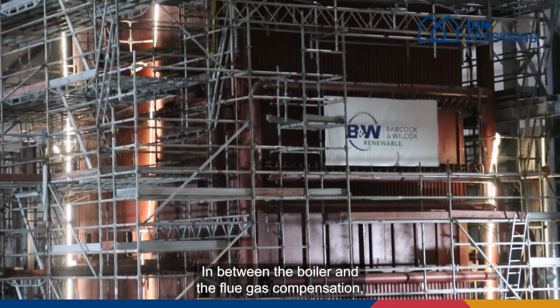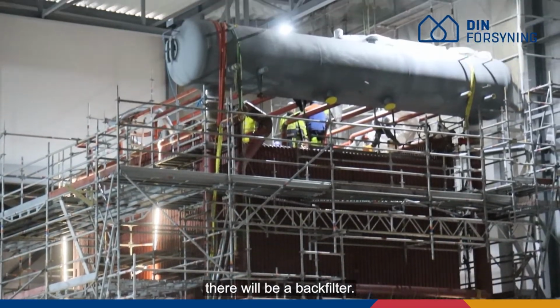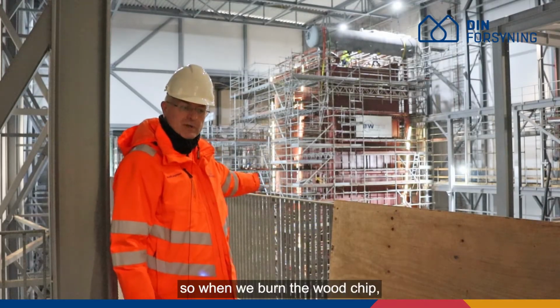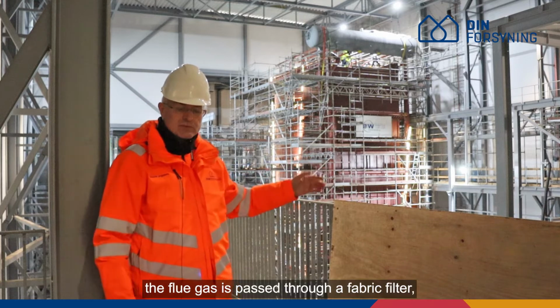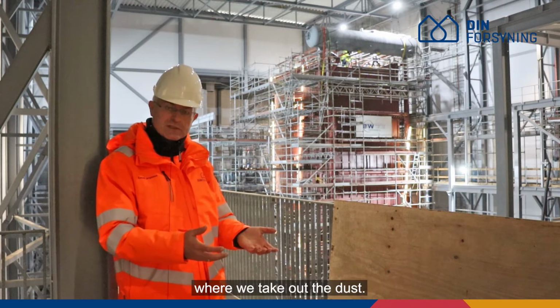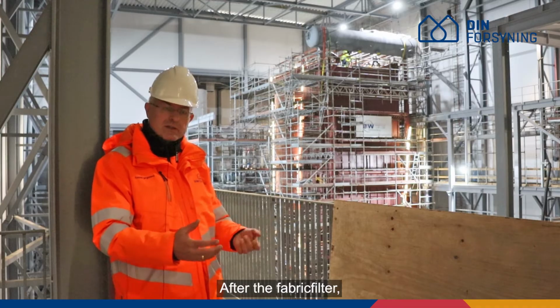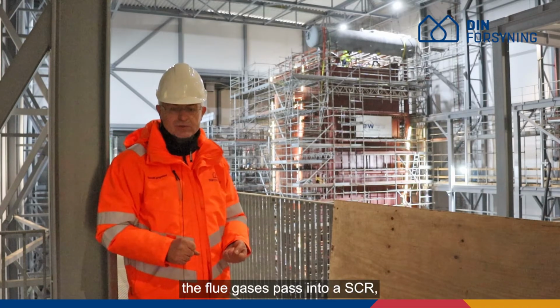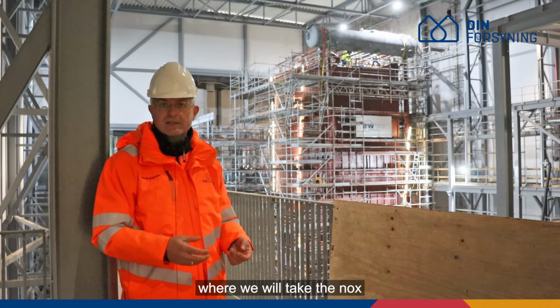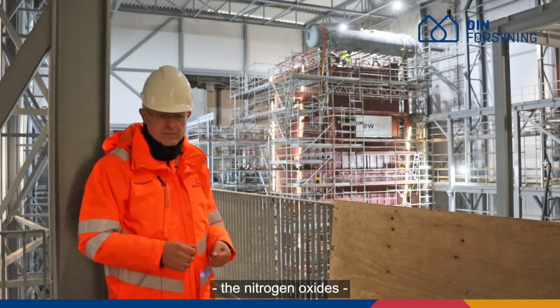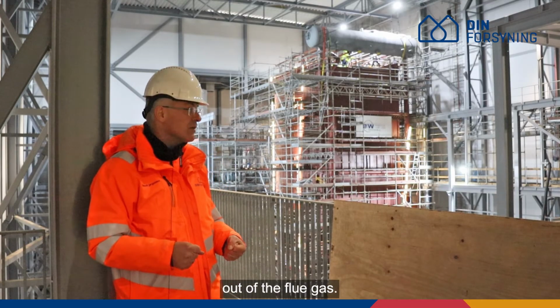In between the boiler and the flue gas condensation, there will be a bag filter. It's not here now, but it will be erected shortly. So when we burn the wood chip, the flue gases pass through a fabric filter where we take out the dust.